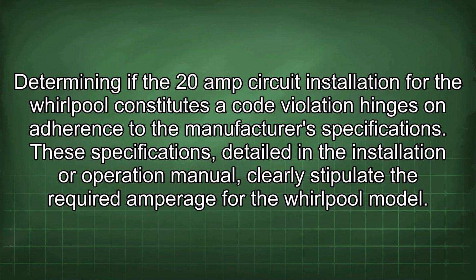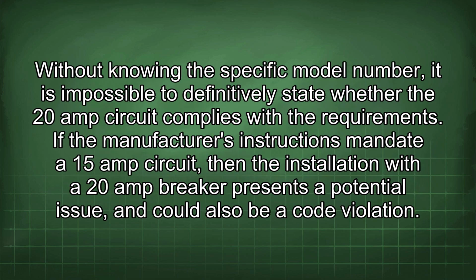Determining if the 20 amp circuit installation for the Whirlpool constitutes a code violation hinges on adherence to the manufacturer's specifications. These specifications, detailed in the installation or operation manual, clearly stipulate the required amperage for the Whirlpool model. Without knowing the specific model number, it is impossible to definitively state whether the 20 amp circuit complies with the requirements. If the manufacturer's instructions mandate a 15 amp circuit, then the installation with a 20 amp breaker presents a potential issue and could also be a code violation.